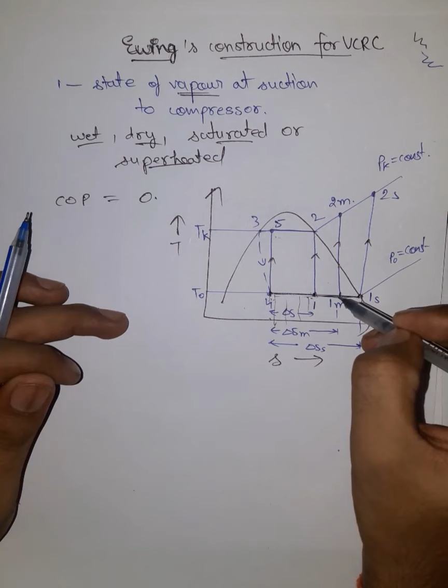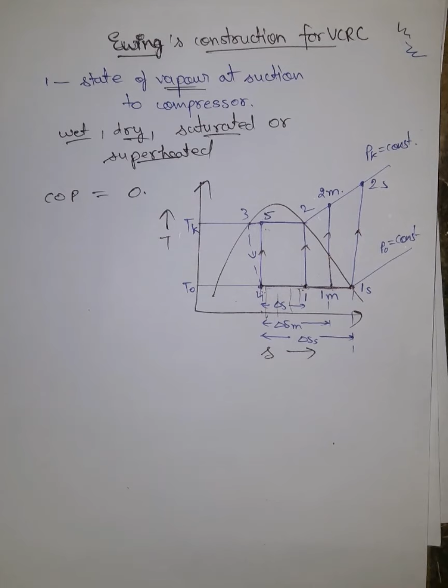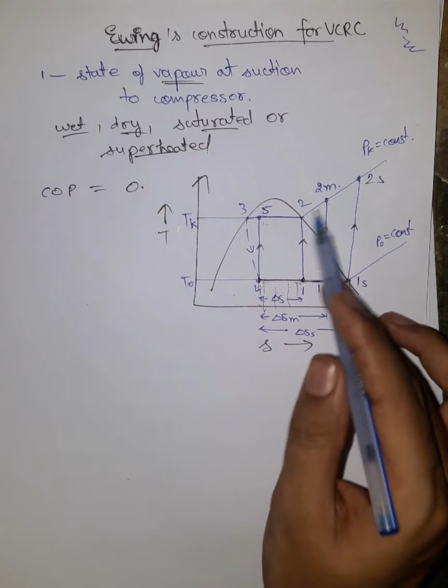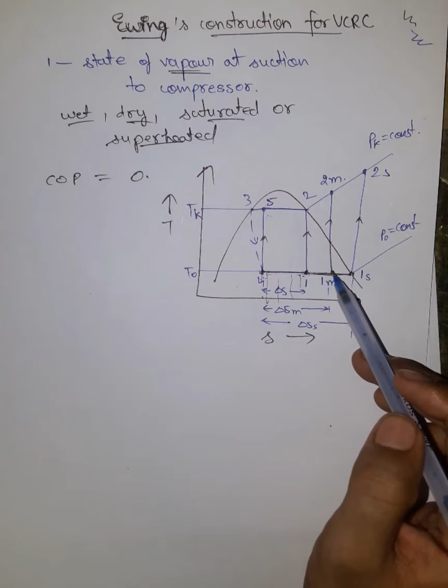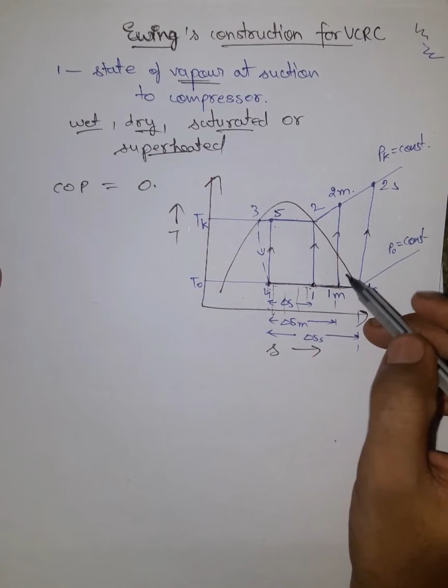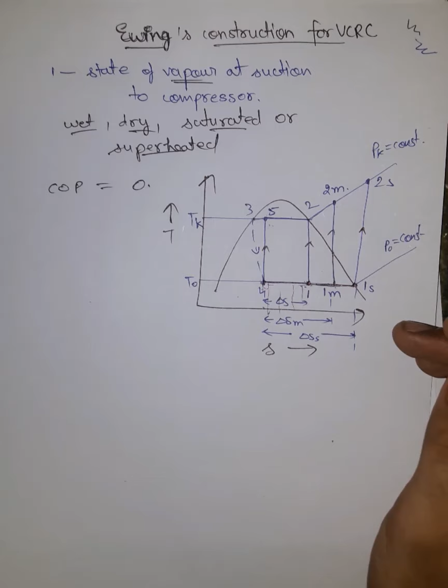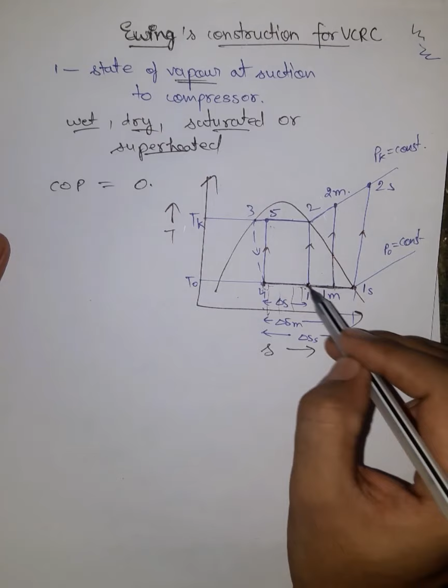Now after this point 1, we can see that if we compress the refrigerant, it is partially in the wet region and partially in the superheated region. So the compression is not totally dry or totally wet. And you can see that heat is not rejected at constant temperature now if the compression is moved further from point 1. And what is the trend seen if we go on moving from point 4 towards point 1S? There is a point in between 4 and 1S at which the maximum COP is reached. And that may be anywhere between 4 and 1S.